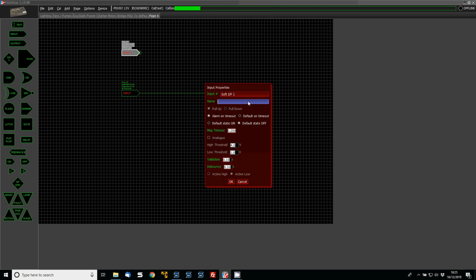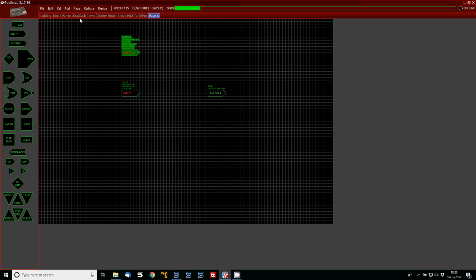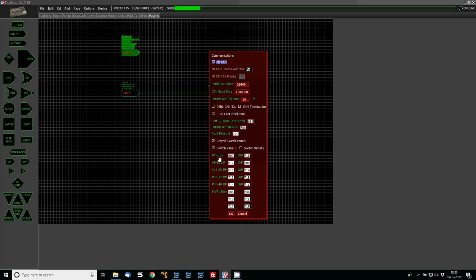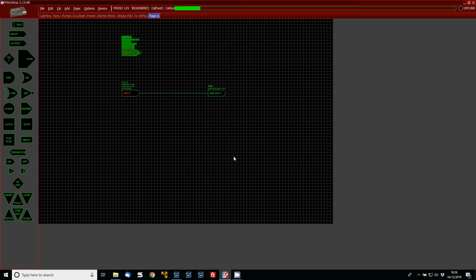So soft input 1, let's call this one radfan 1. Now once you've done that, we need to go to Cal and Communications and set our soft inputs to be on the same identifier. We're going to use the 400 identifier, so put in there 400, and you'll see straight away CAN 0x400 byte 1 of 8 is going to be this soft input.